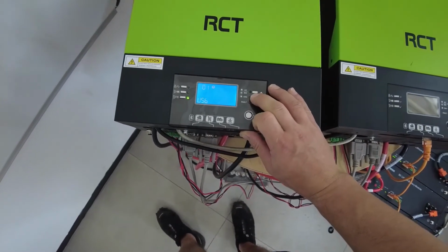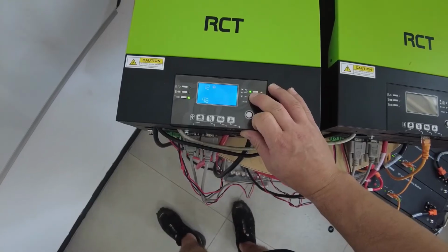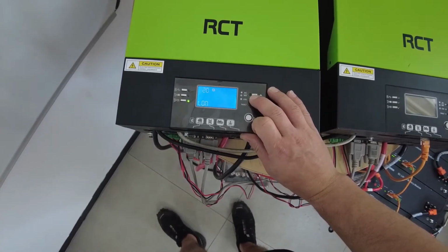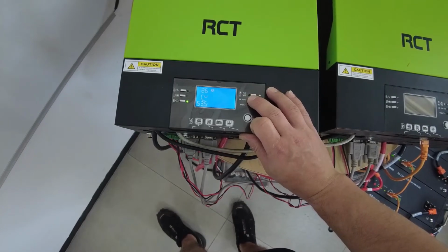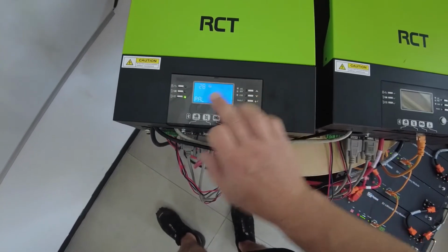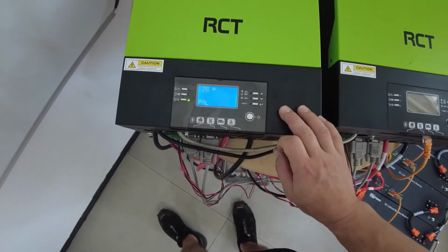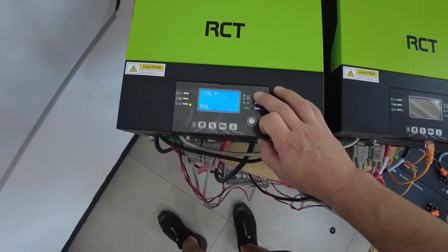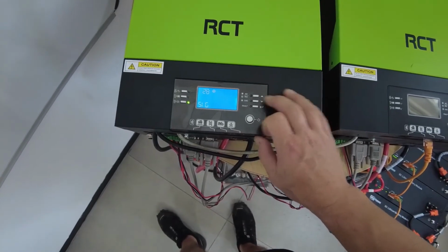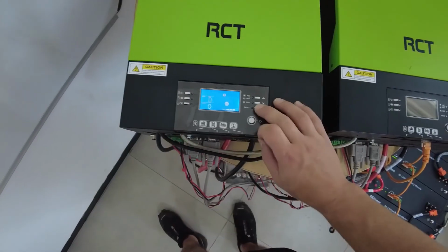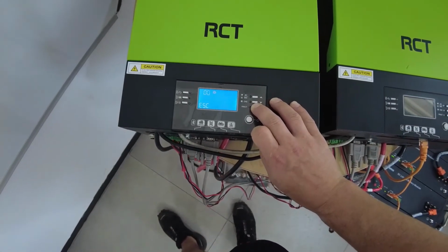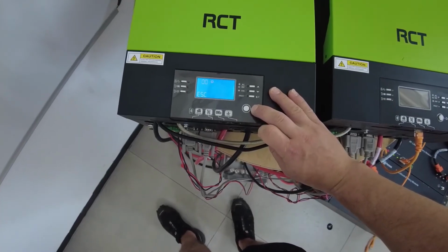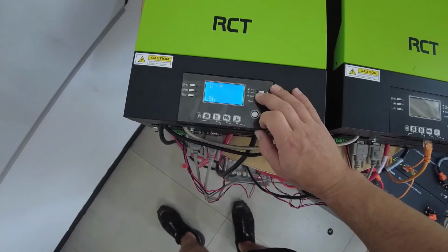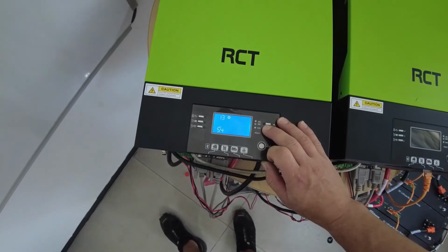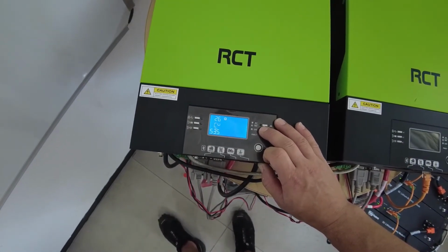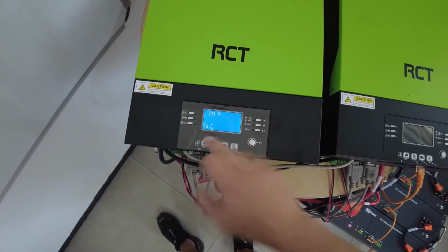So for argument's sake, going down to setting number 28. Before you press the enter button, switch off the inverter, press enter, and then you can change the setting. Press enter. It's now on SIG. Now the inverter will switch off if you do not switch it on again. Switching it on, we can go down again to setting number 28. As you can see, that makes its change.